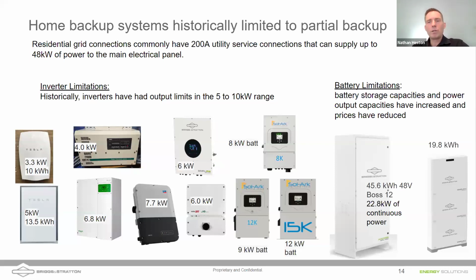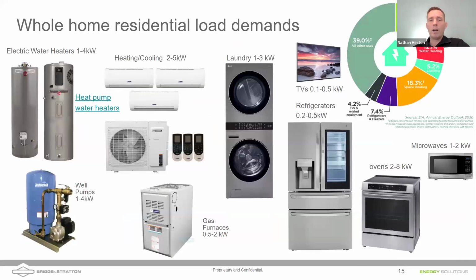In terms of battery limitations, batteries have a storage capacity, but they also have output limitations as well. So typically batteries are rated at a C/3, C/2. Our batteries are C/2 power limitation. That means that you can draw the power out of the batteries as fast as in 3 hours or 2 hours. And the battery on the right, our newest battery, is going to be offering a considerably higher power draw rate. I believe it's going to be a 1C power rating, which means that you can discharge it quickly because it's designed in a way to be able to provide that power without damaging cells.